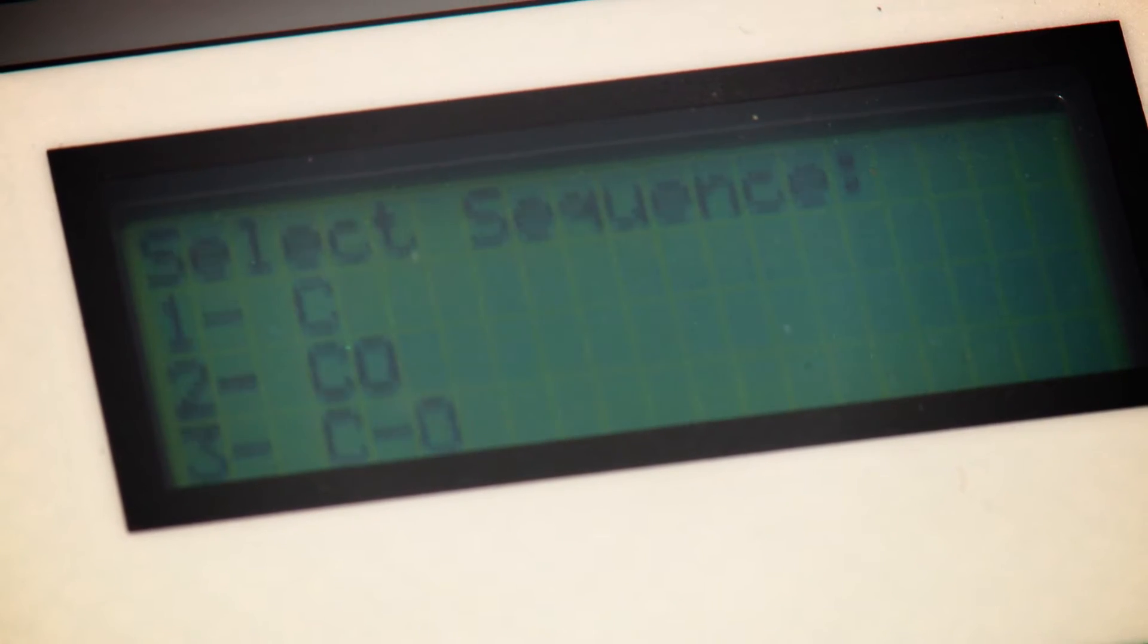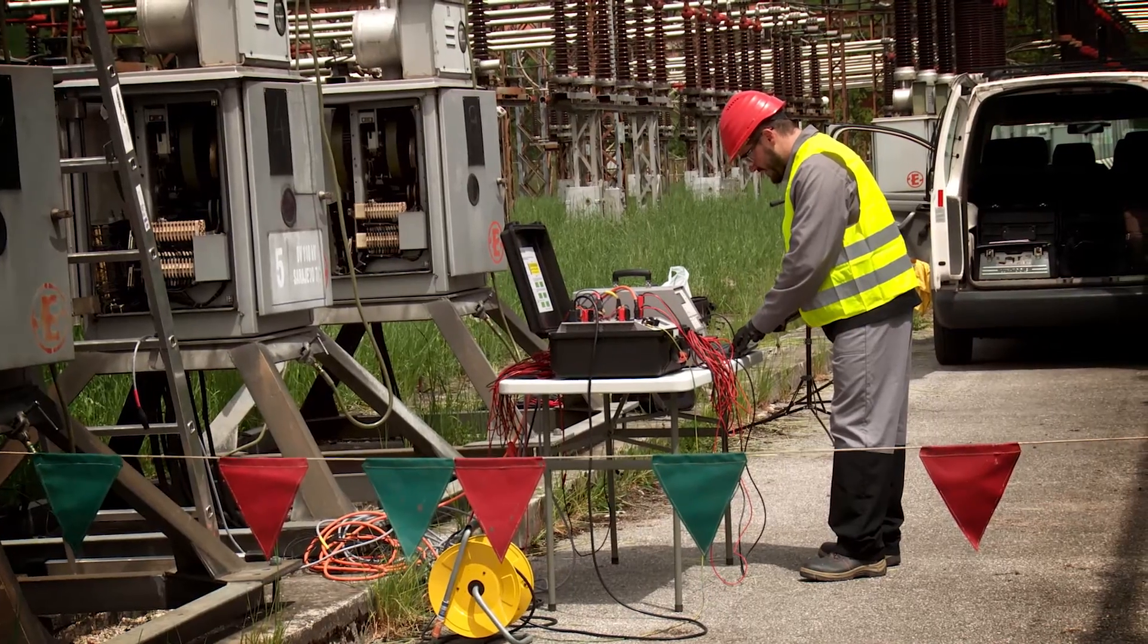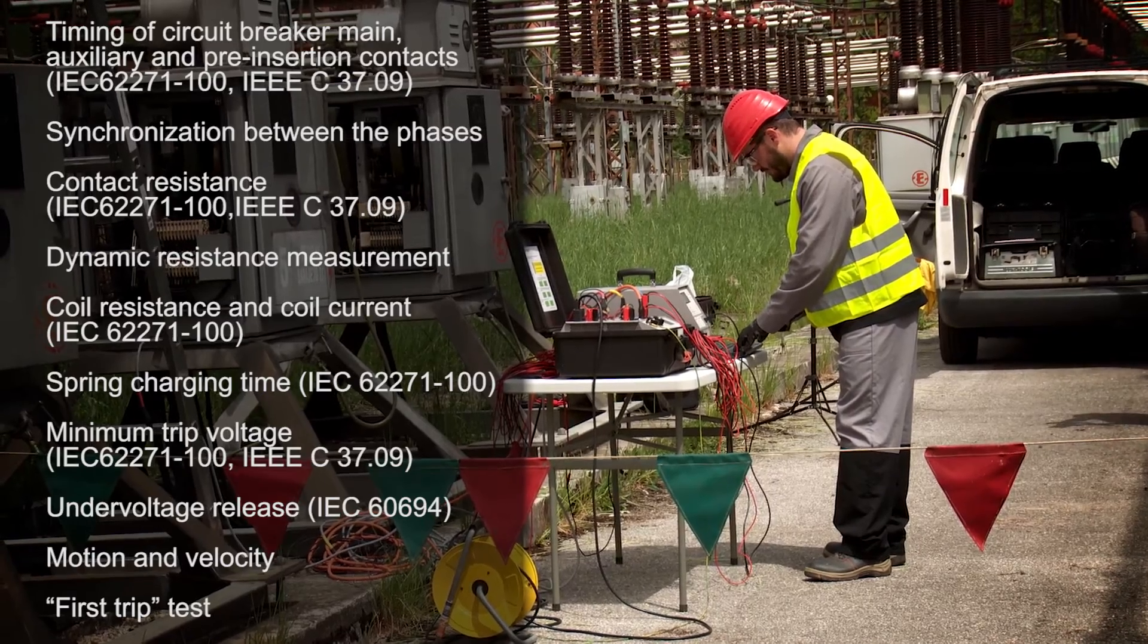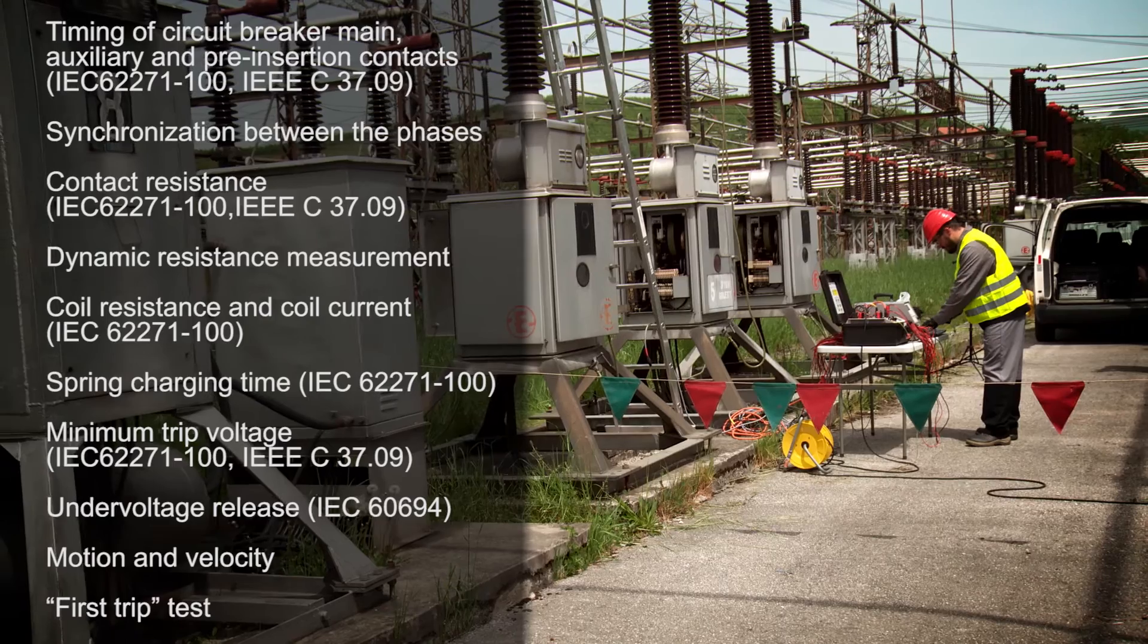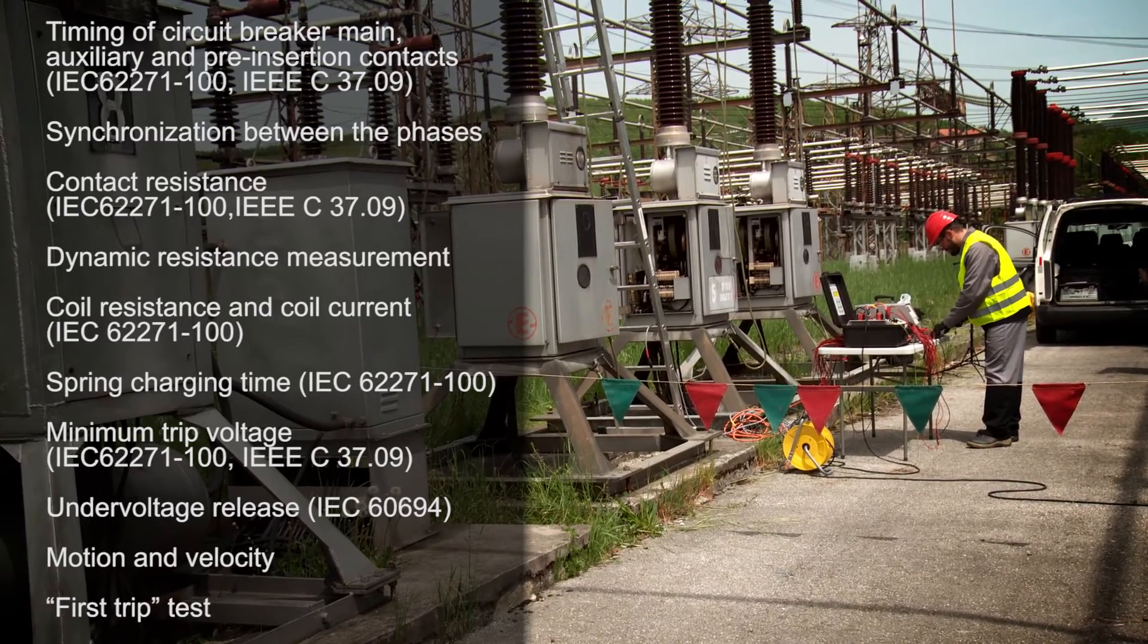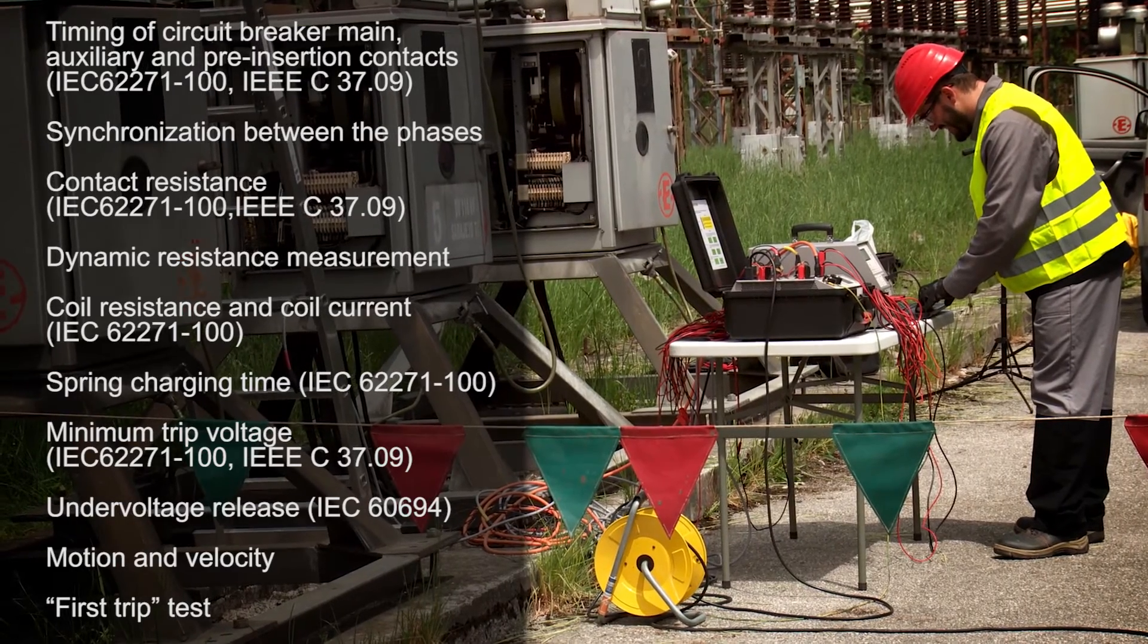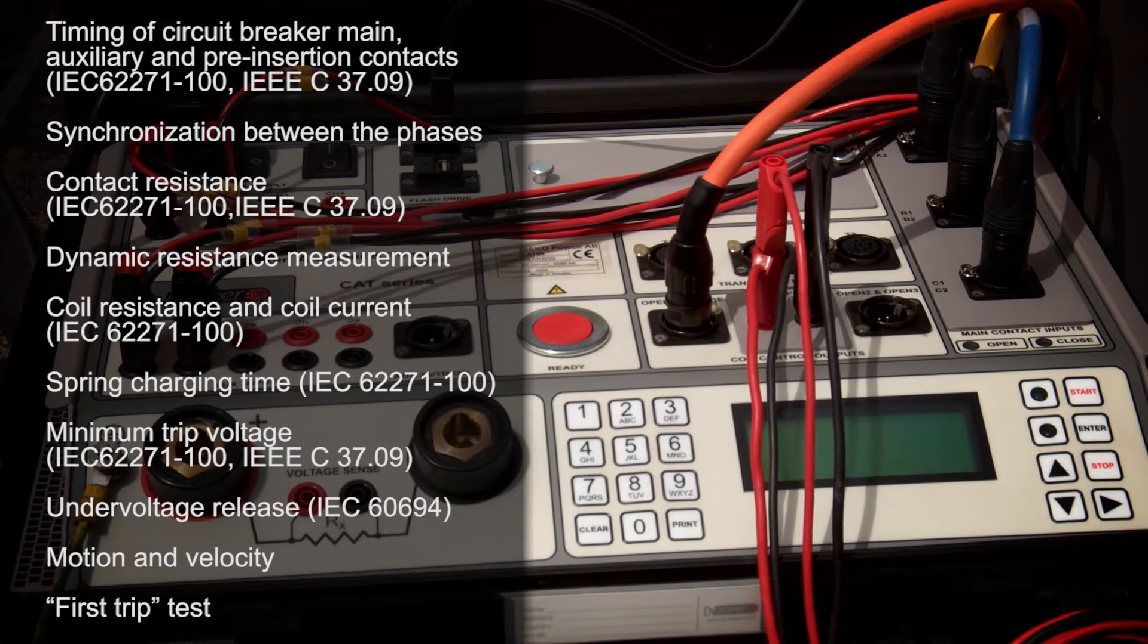Applications supported by DV Power circuit breaker test equipment include measurements of timing of circuit breaker main, auxiliary and pre-insertion contacts, synchronization between the phases, contact resistance, dynamic resistance measurement, coil resistance and coil current, mechanism charging time, minimum trip voltage, under voltage release, motion and velocity, and first trip test.